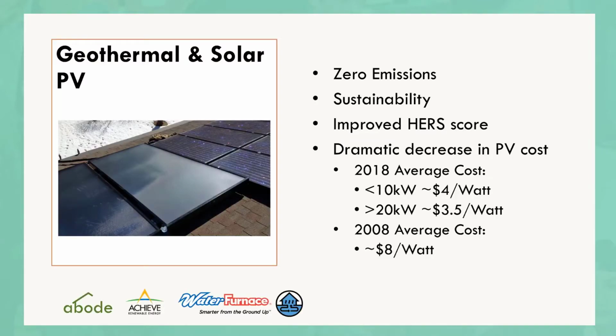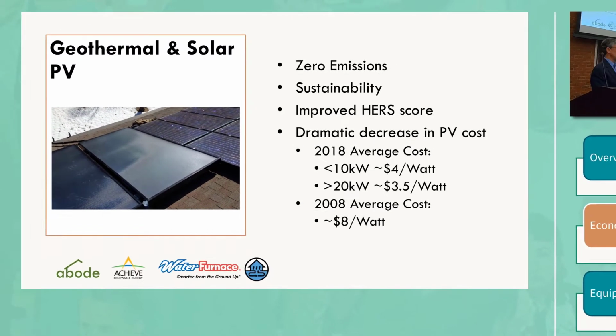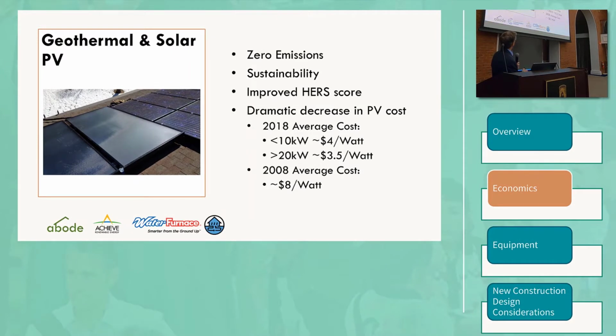Ground source heat pumps pair very well with both solar technologies. This slide shows solar photovoltaic modules here for generating electricity and solar thermal modules here. The PV is the most straightforward. If you're switching to an efficient electric-based heating system like geothermal, you put up PV, you're going to offset the electric use directly and can get to net zero through that approach. Solar thermal or solar hot water systems can be used for hot water in conjunction with the geothermal system. It's also possible to dump heat from the solar thermal system into the geothermal ground source and store it there for winter use.